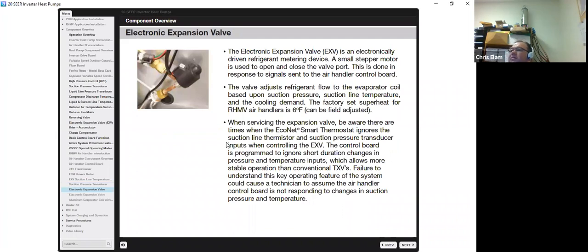You also have your electronic expansion valve. When you think about EEVs, the electronic expansion valves, they basically come in 3 components. You have your controller, which could be the RCF small board, which we'll get into. It can be the air handler control board, or in the case of the outdoor unit, it can be the variable speed control board. So you have your EEV, which is the black rubber piece here. That's your motor. You have your actual EEV valve body, which is the copper, and then you have your control.